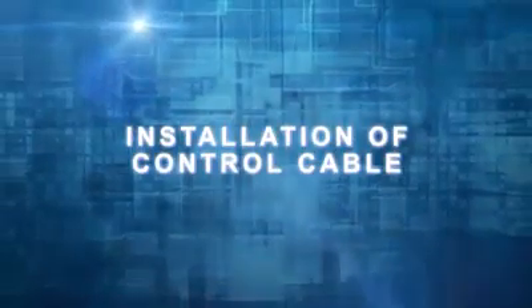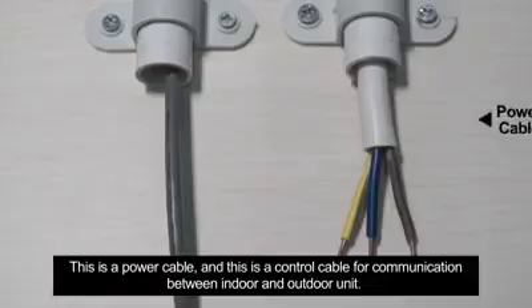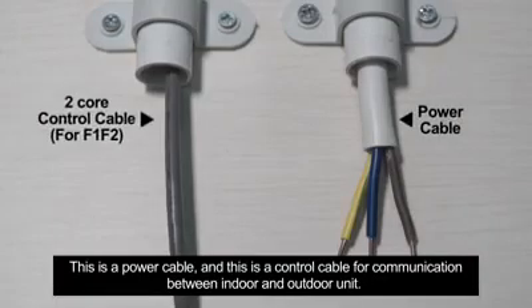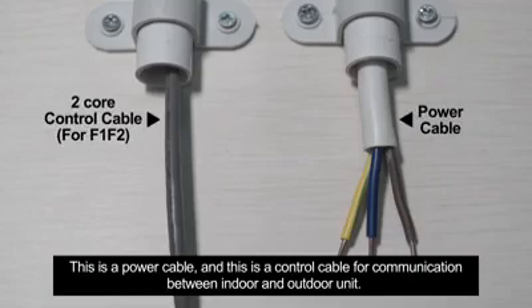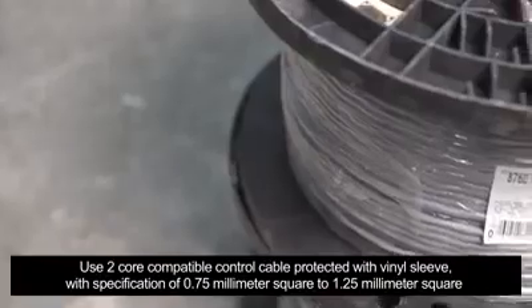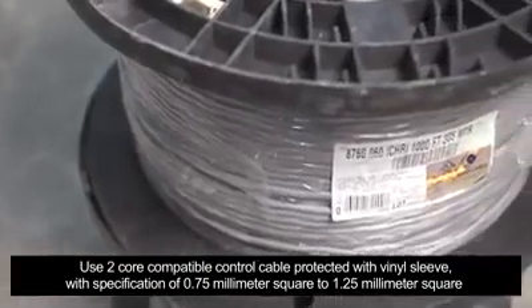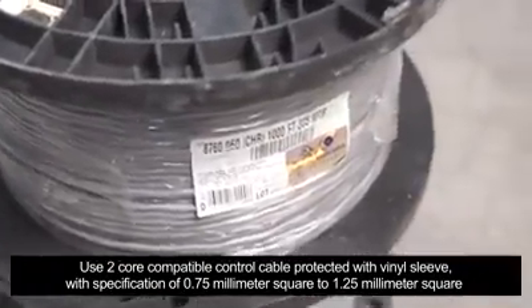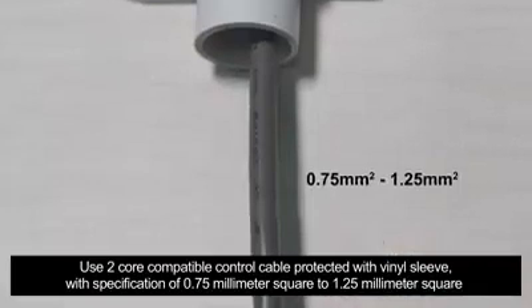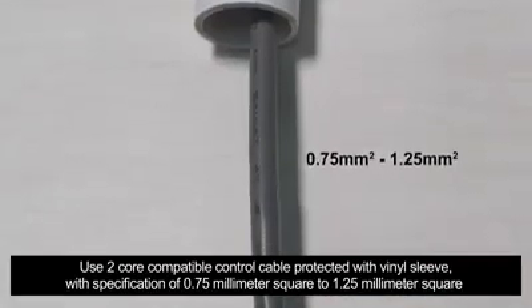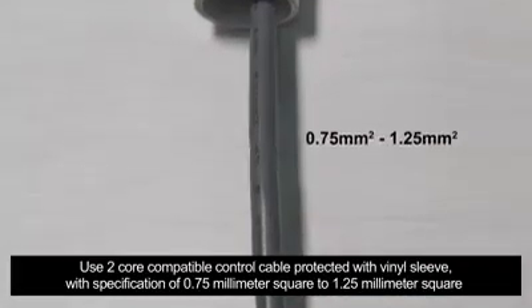Installation of control cable. This is a power cable, and this is a control cable for communication between indoor and outdoor unit. Use 2-core compatible control cable protected with vinyl sleeve, with specification of 0.75 mm square to 1.25 mm square.